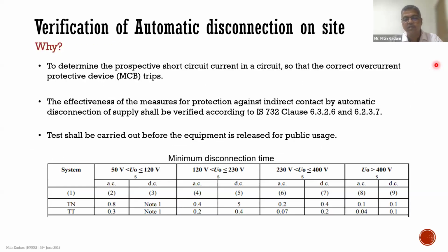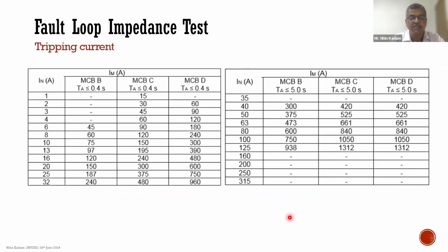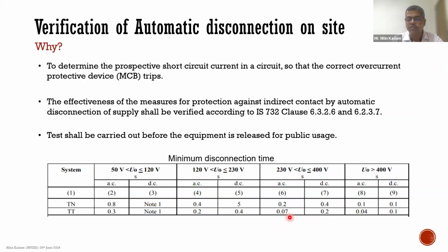So these are, in the previous chart, you'll see here. This is a chart that is applicable in case of AC circuits. If it is a TN network, 0.2 seconds is the tripping time. In case of a TT network, 0.07 is the tripping time that is required. So the tripping time should not be higher than this. If it is lower, it is welcome. Sorry, at the max 0.2 or 0.07.